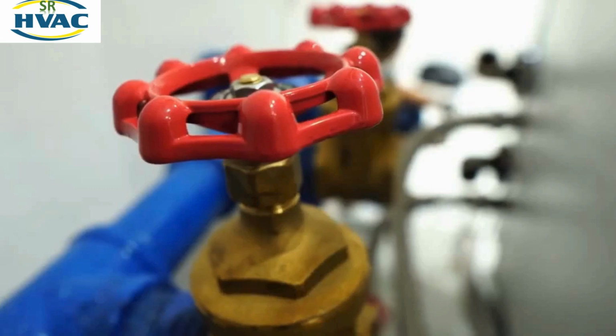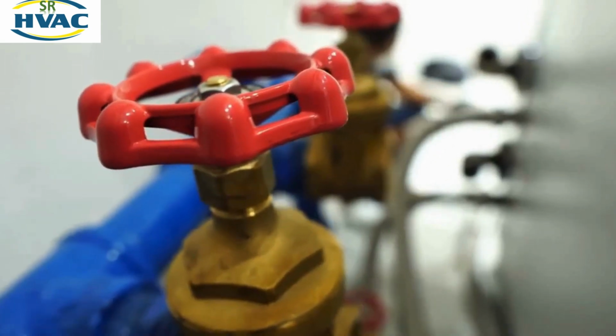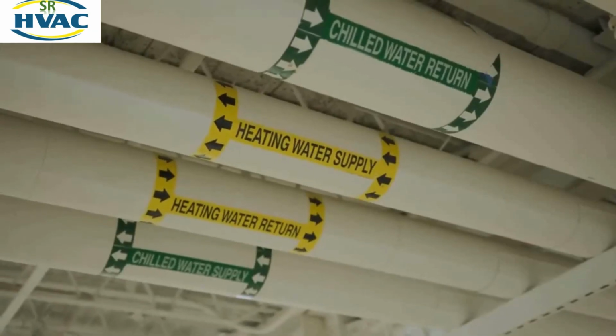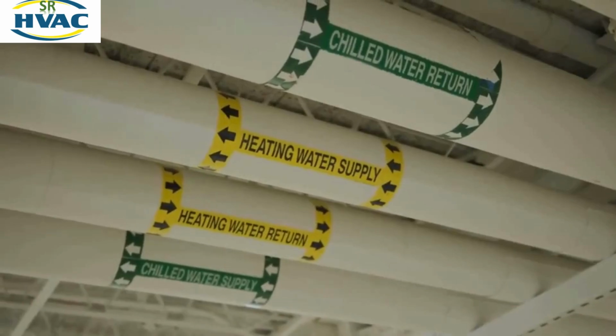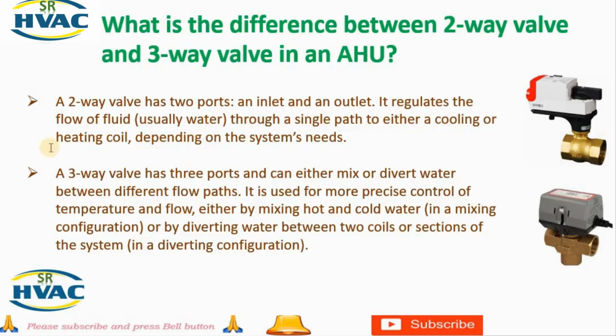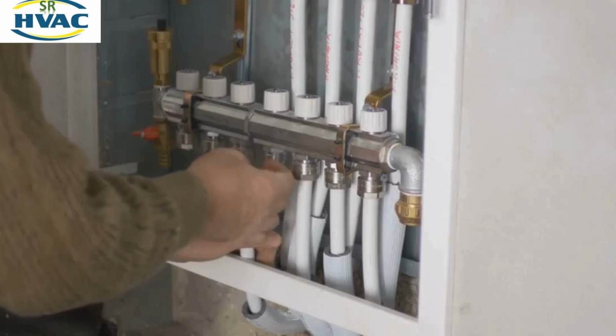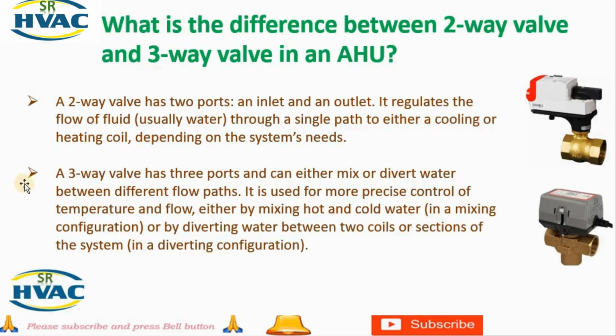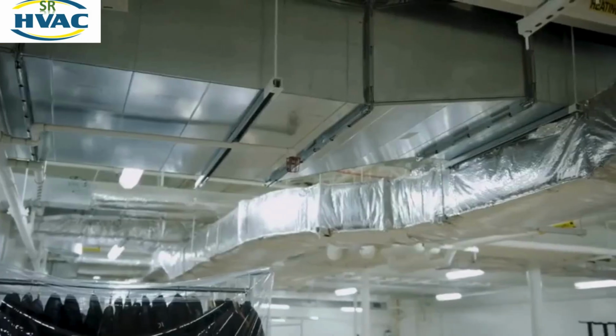A two-way valve has two ports, an inlet and an outlet. It regulates the flow of fluid, usually water, through a single path to either a cooling or heating coil, depending on the system's needs. A three-way valve has three ports and can either mix or divert water between different flow paths. It is used for more precise control of temperature and flow, either by mixing hot and cold water in a mixing configuration or by diverting water between two coils or sections of the system in a diverting configuration.